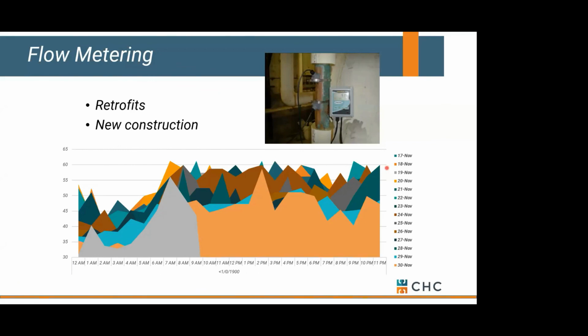One thing that's been really successful for any retrofit or existing project is going in with a water meter and using that water meter to track the existing building load. You can forecast that out for 100% occupancy. And you give an owner a really nice report that says, "Hey, I know your water heaters are sized for X gallons a minute, but based on your water meter and 100% capacity, you're not close to that." To right size a water heater is pretty important these days, and that's the power of a water meter.